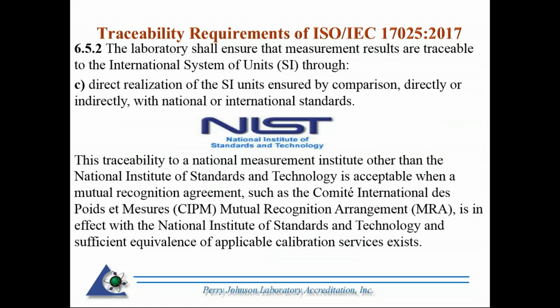Okay, you can assure that measurement results are traceable to the SI through the NMI, direct realization of the SI ensured by comparison, directly or indirectly, with national or international standards. So I've got NIST referenced there, the National Institute of Standards and Technology. That's the NMI in the United States, which is perfectly acceptable, of course, going directly to NIST for your traceability. Or you can go to another NMI that's under the same mutual recognition agreement through the International Committee for Weights and Measures, the CIPM, and it's written in French there. You can see what that stands for. I'll just refer to it as CIPM Mutual Recognition Arrangement.